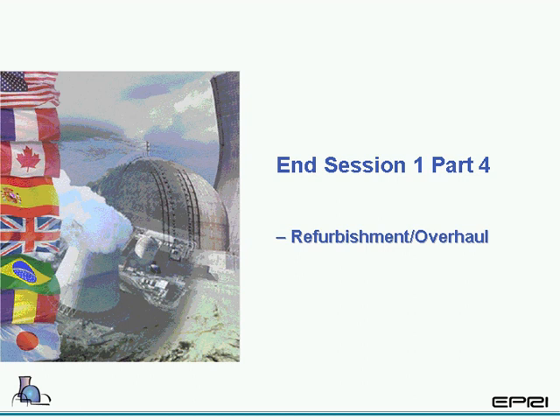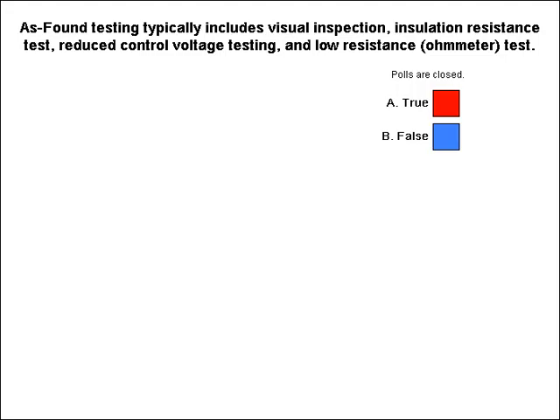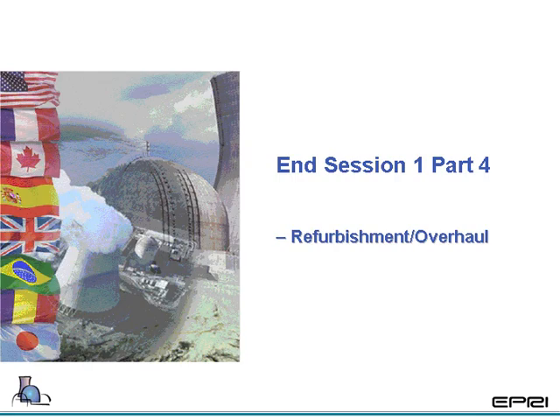I went to 5 and 6. All right, and that should pretty much complete the overhaul. Now, we were taking a look at Session 1, Part 4. Don't pay attention to all the slides bouncing around, just that one. What we're looking at here is refurbishment and overhaul as far as preventative maintenance. As spoken about, you will perform all these tasks and then step into the as-left testing of the breaker. In other words, you're going to redo all the visual inspections that were performed in the preventative maintenance, and then check your latches, latch bites, and do your testing as stated in the preventative maintenance.